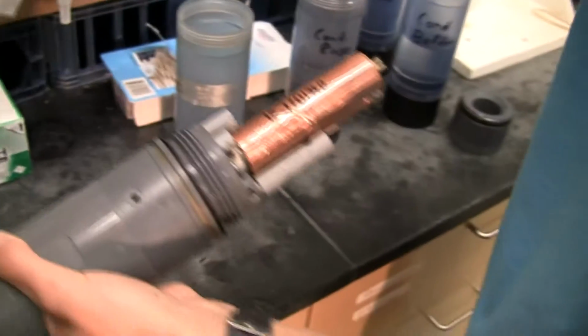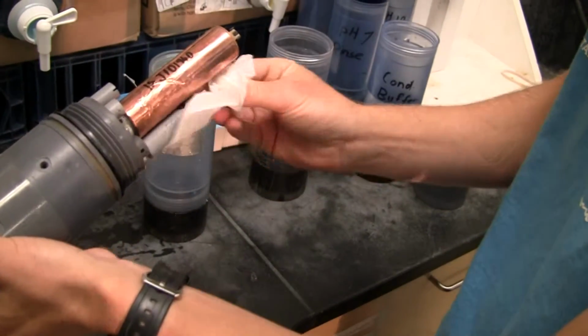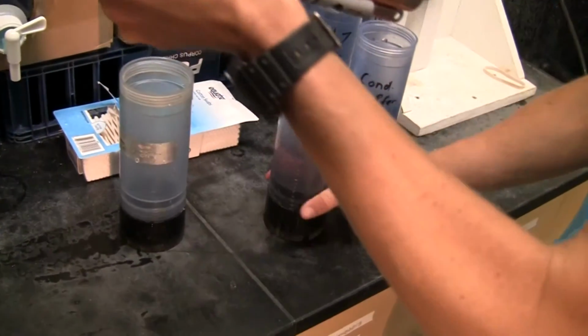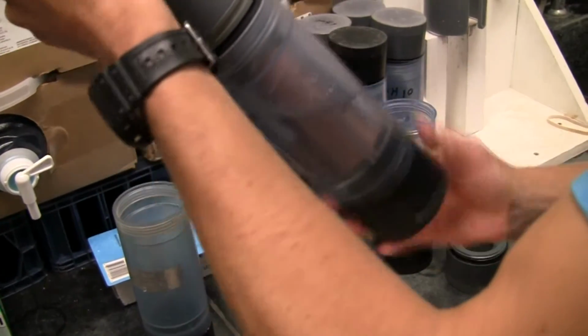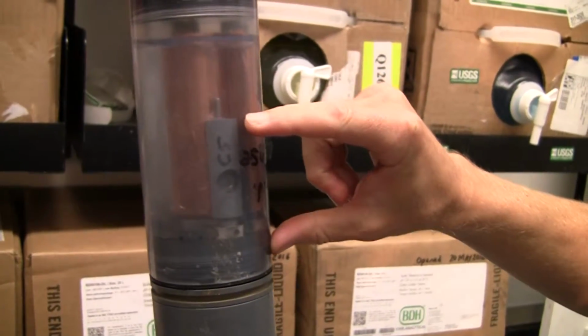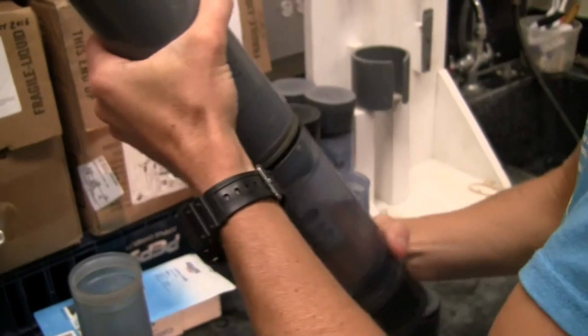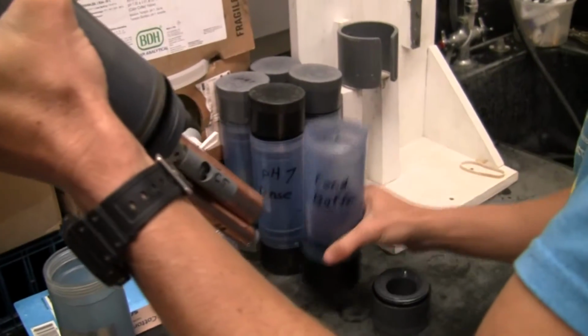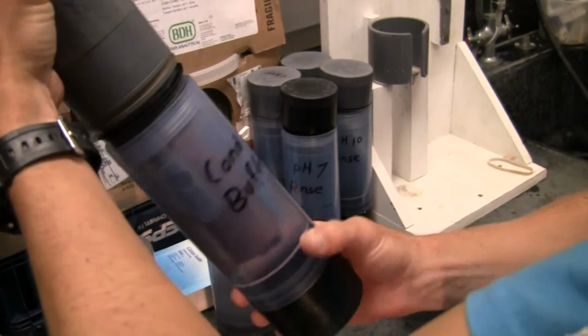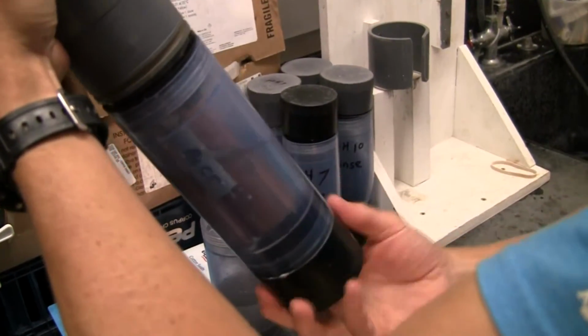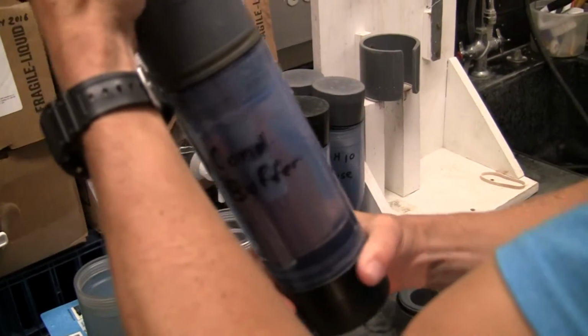Now we place the sensor heads in the conductivity rinse, and we need to verify and check that we actually have enough standard, enough to fill the sensor. Okay, so we verified that we do have enough, so now it's rinsed. Now place inside the buffer solution, which is what we're going to be calibrating against. Again, to verify that we actually have enough solution, which we do.